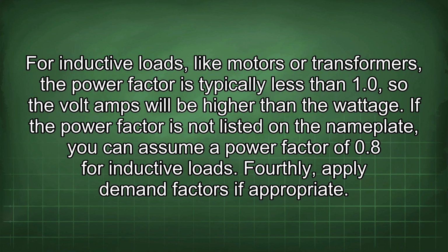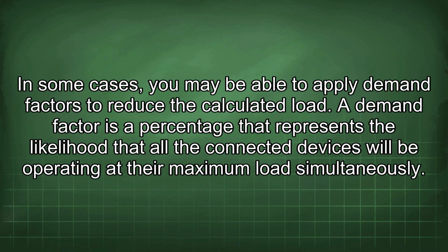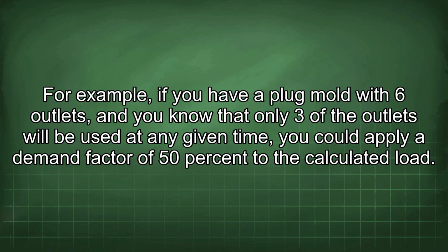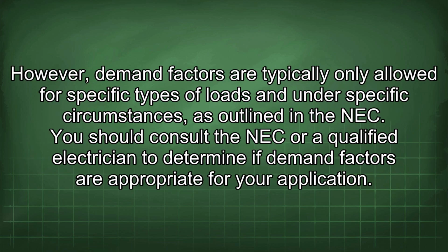Fourthly, apply demand factors if appropriate. In some cases, you may be able to apply demand factors to reduce a calculated load. A demand factor is a percentage that represents the likelihood that all the connected devices will be operating at their maximum load simultaneously. For example, if you have a plug mold with 6 outlets, and you know that only 3 of the outlets will be used at any given time, you could apply a demand factor of 50% to the calculated load. However, demand factors are typically only allowed for specific types of loads and under specific circumstances, as outlined in the NEC. You should consult the NEC or a qualified electrician to determine if demand factors are appropriate for your application.